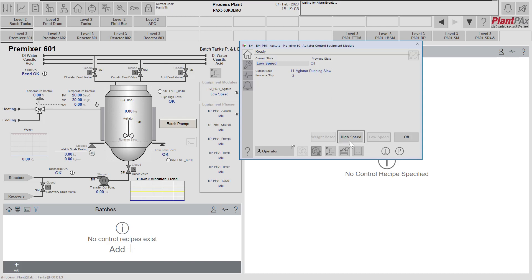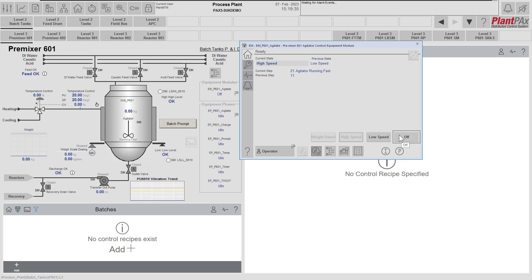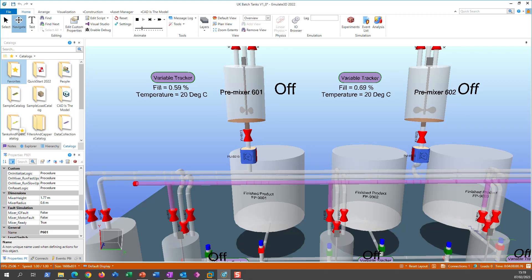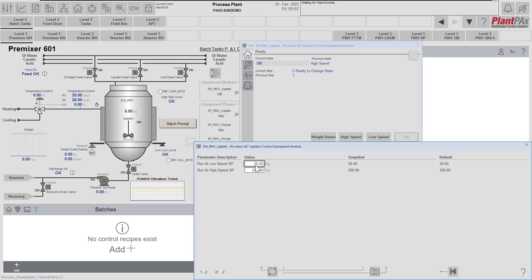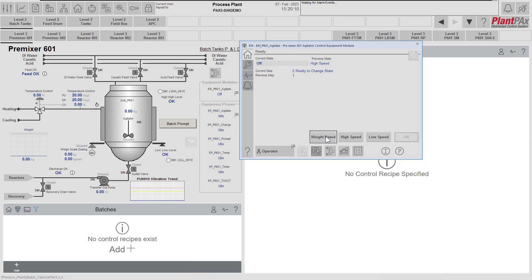Let's move to high speed mode. Buttons disable while transitioning, then from high speed the available states are low speed and off. The agitator is now running fast. Then let's switch to the off state. The agitator stops. Now let's go to the weight-based state, where we use the module parameters. In this mode we monitor the incoming weight: if it's higher than 50 kilograms the agitator runs at low speed, if higher than 200 it runs at high speed, and if less than 50 the agitator won't run.